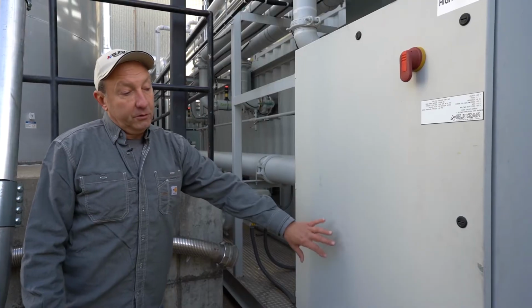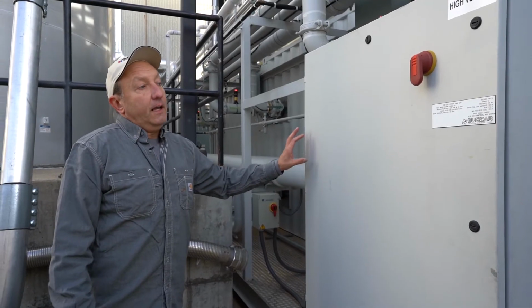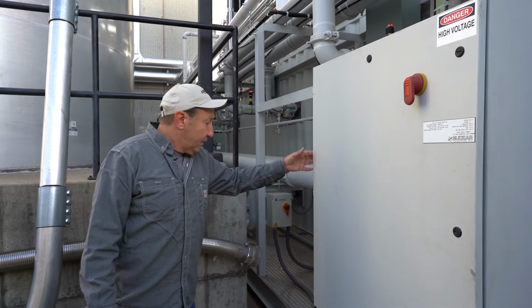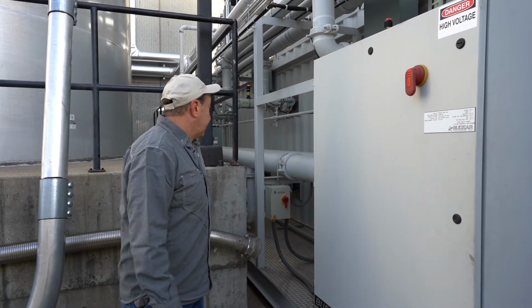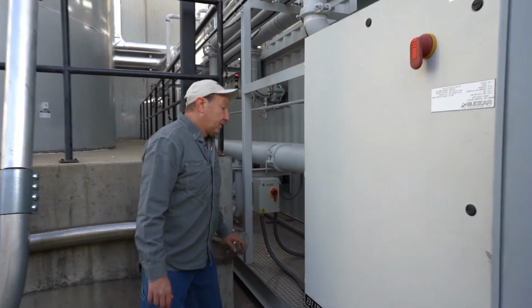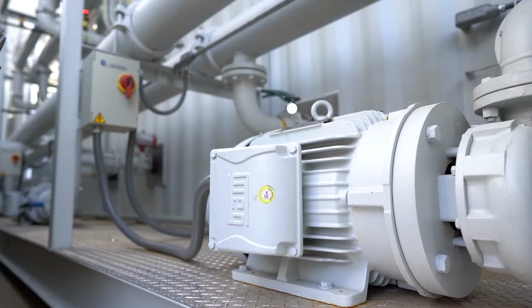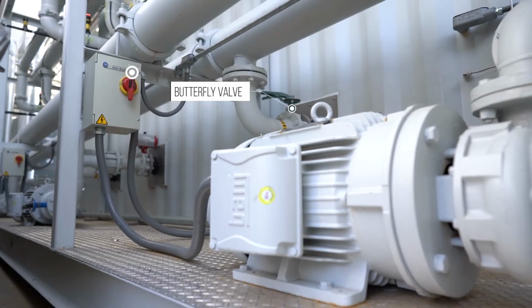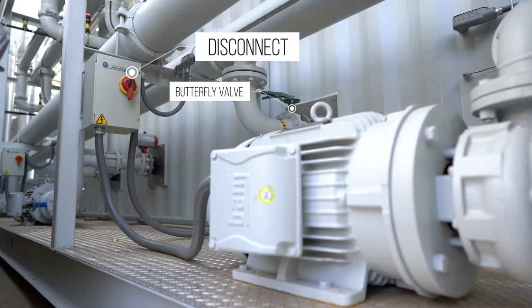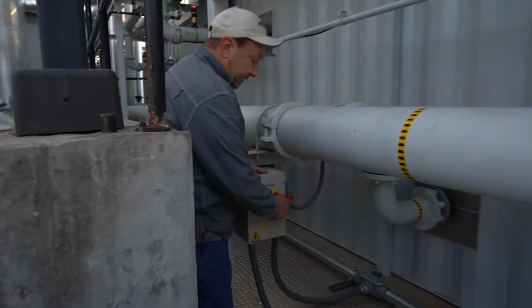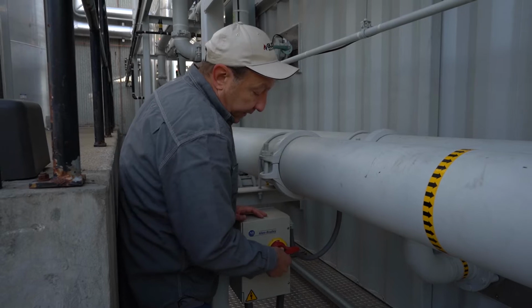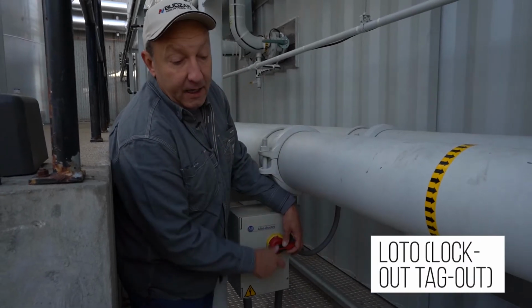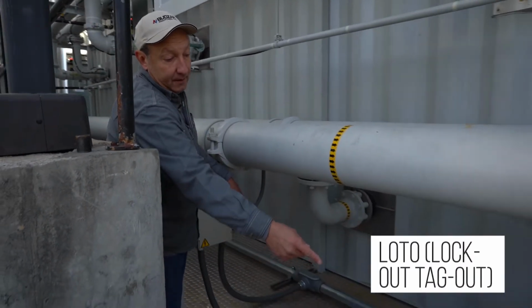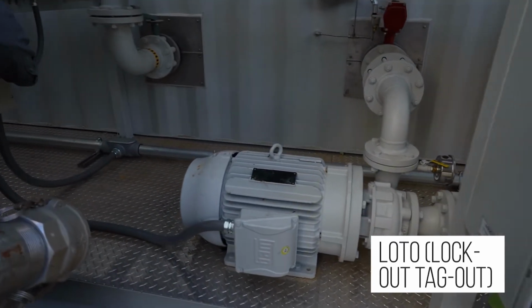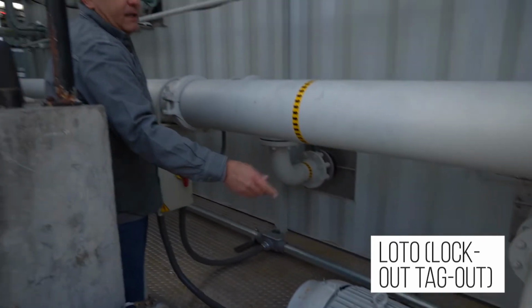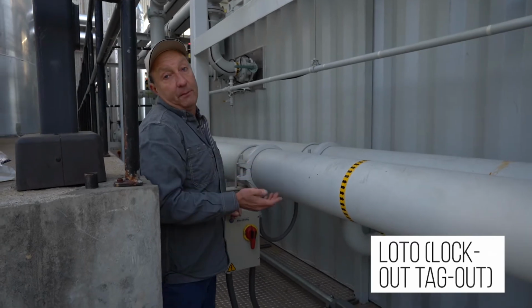Inside here, there's an enclosure heater, there's contactors, and a small I/O rack for the instrumentation. Each pump, similar to the pumps up above, can be isolated by butterfly valves, and each has a disconnect. So I can lock this motor out safely. I can put the lockout/tagout on here, and I can safely work on this pump. It's got an independent drain, isolation valves, and we could maintain this pump and utilize the other 2 and keep the process up and running.